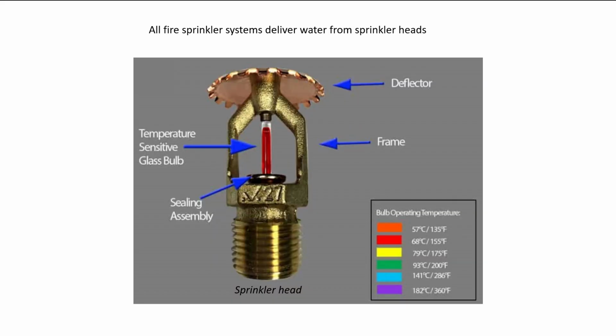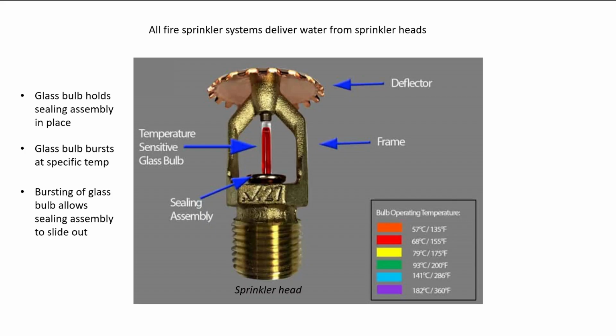All fire sprinkler systems deliver water from sprinkler heads. They're made up of a deflector, a frame, a sealing assembly, and a temperature-sensitive glass bulb that's all threaded into a standard steel or plastic water supply pipe. The temperature-sensitive glass bulb holds the sealing assembly in place. The glass bulb bursts at a specific temperature, and the glass bulb is filled with an alcohol solution that is designed to break through the glass tube wall that houses it at a specific temperature, and that temperature is easily identifiable visually by the color of the alcohol inside. Bursting of the glass bulb allows for the sealing assembly to then slide out.